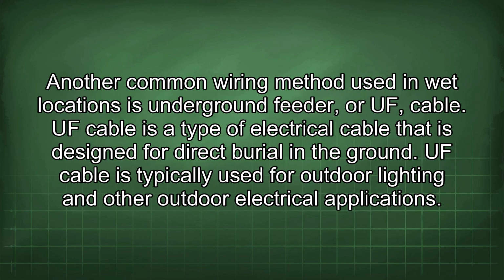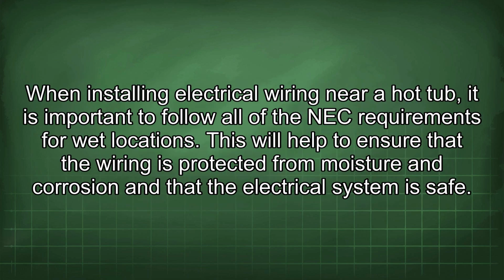Another common wiring method used in wet locations is underground feeder, or UF cable. UF cable is a type of electrical cable that is designed for direct burial in the ground. UF cable is typically used for outdoor lighting and other outdoor electrical applications. When installing electrical wiring near a hot tub, it is important to follow all of the NEC requirements for wet locations.